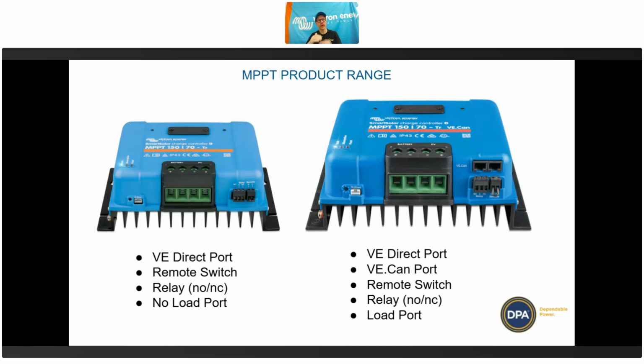But normally you want your open circuit voltage to be about 10% below the top threshold, because the open circuit voltage on the spec sheet is at standard test conditions. If the panel is really cold and gets a sudden burst of light, then that voltage can be higher than the open circuit voltage. So you want to give yourself a little bit of wiggle room. Don't design it to be bang on the top value, because you will break it.